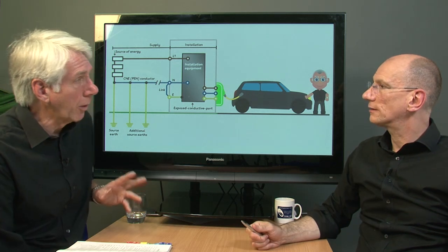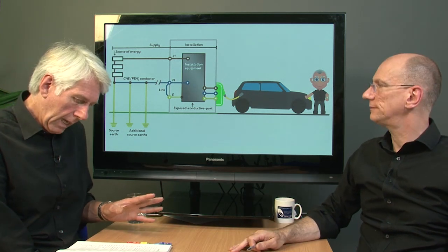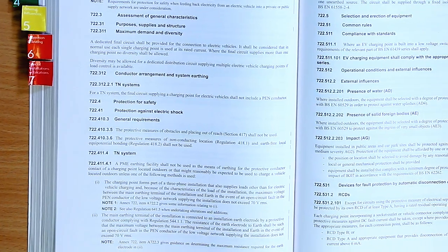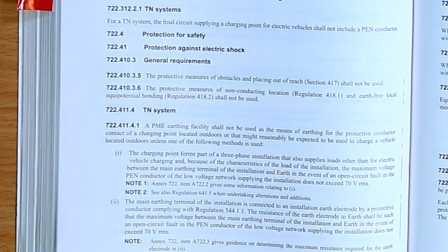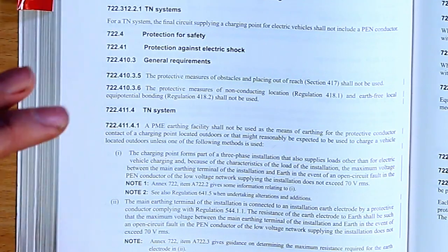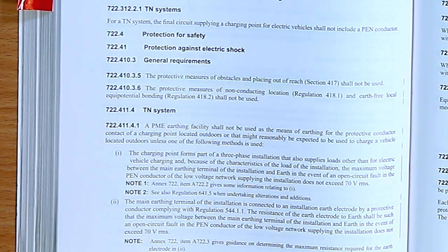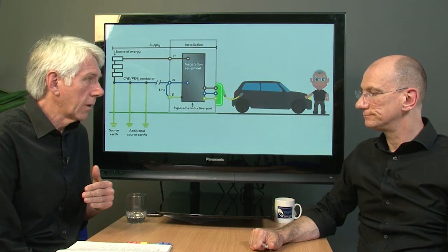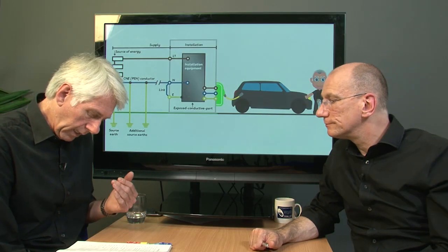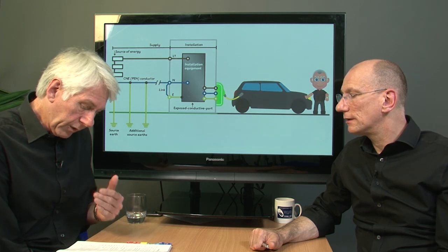So there's the problem the regs are trying to sort out. When we look to 722.411.4.1, it talks about that very situation: in a TN system, a PME earthing facility shall not be used as a means of earthing for the protective conductor contact to a charging point located outdoors, or that might reasonably be expected to be used outdoors. It gives us three options effectively as supplementary protection if we want to do that.